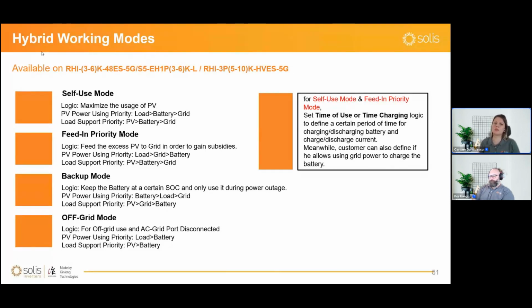There is also a backup mode where you can set a certain value of a reserve for your battery. So you will always keep a certain percentage, like 50%, 80%, as a reserve in your battery, just in case. For example, if you live in areas where you have frequent power outages, you might always want to have a reserve in your battery. So this backup mode can work in parallel either with self-use mode or with feed-in priority.